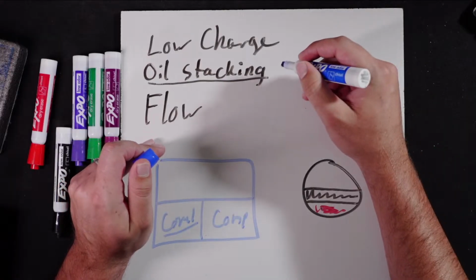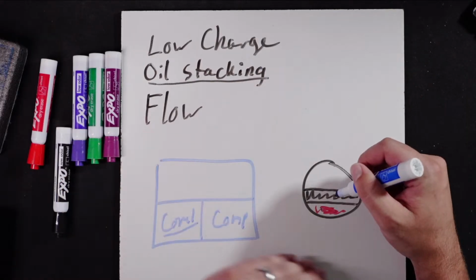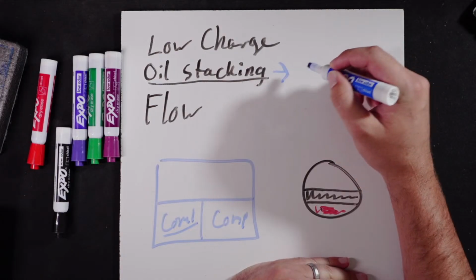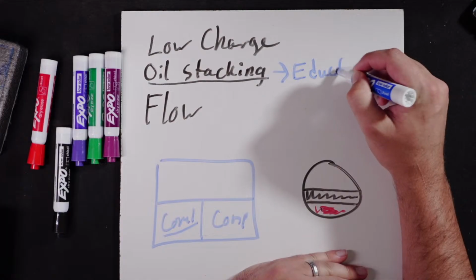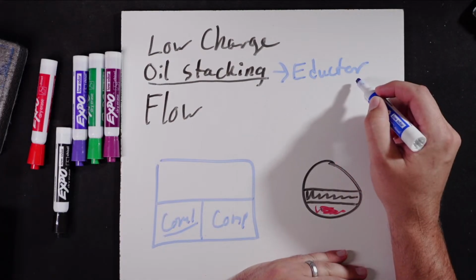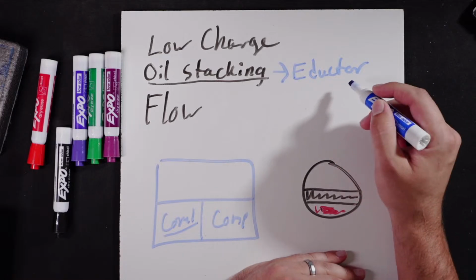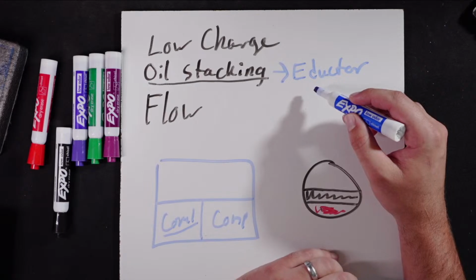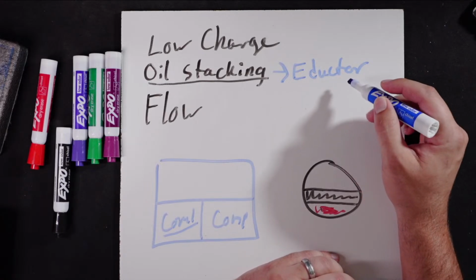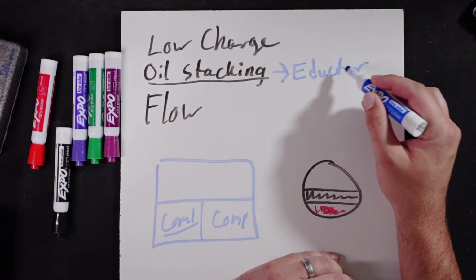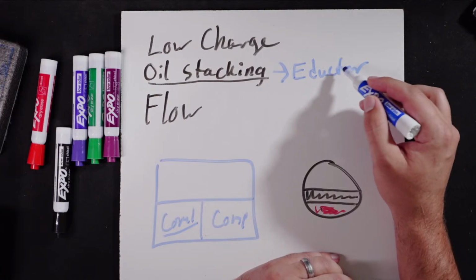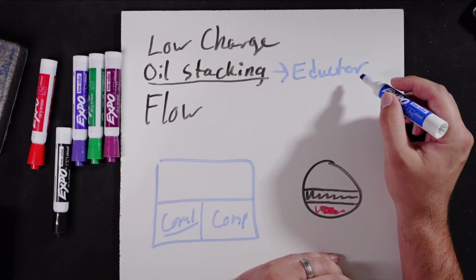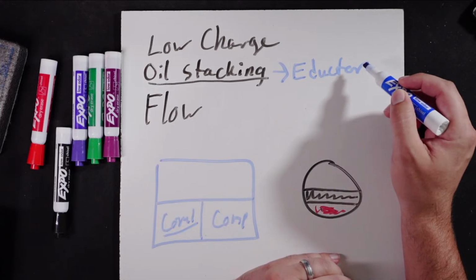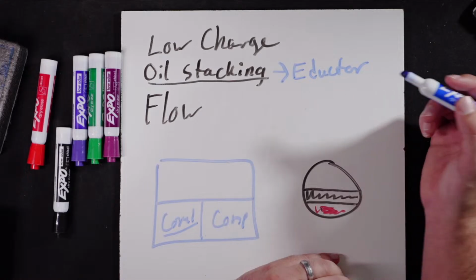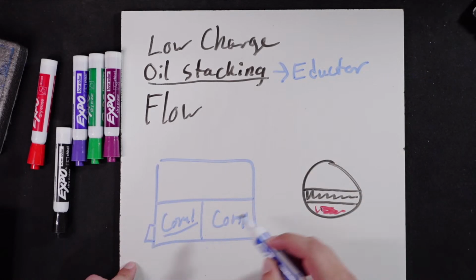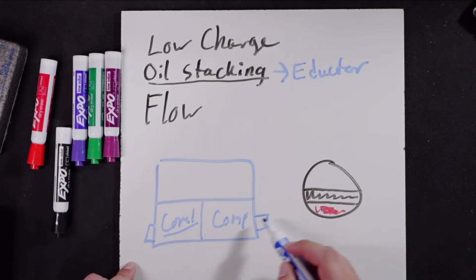suction limiting alarm. Now, if we were having an oil stacking issue based off of the sight glass, I would really want to go through that eductor system. We need to make sure that the filter dryer is in good condition. It's not causing a pressure drop scenario, and we need to make sure that we've got sufficient head pressure, condenser pressure pushing into the eductor. That has everything to do with how well that eductor functions. So if we have really low ambient conditions and our condenser fans are not staging properly for any reason, that's going to affect how well our eductor can function, which the condenser fans on this machine are going to be variable speed. Over here by the compressor, there is your drive cabinet on either side for your condenser fans.